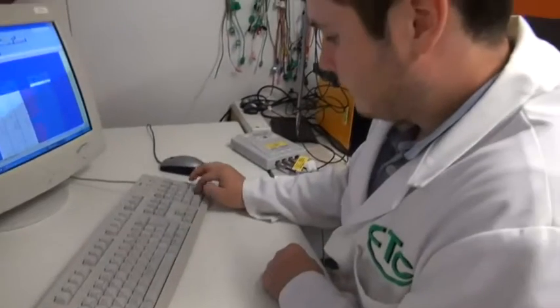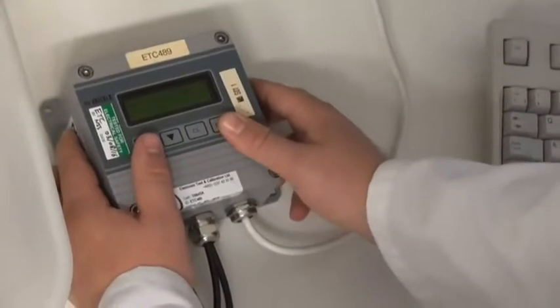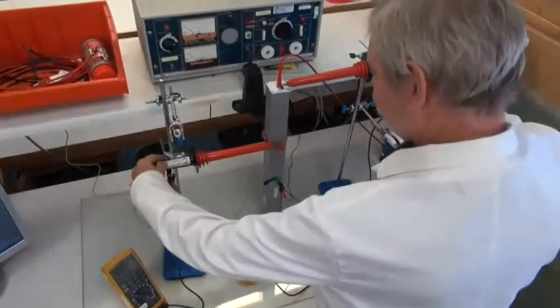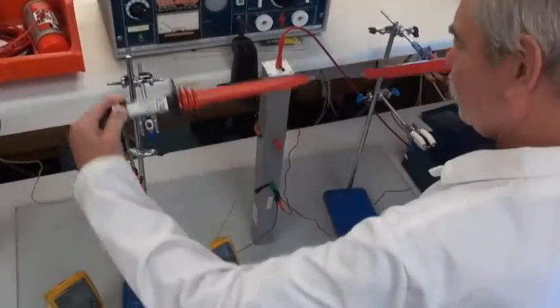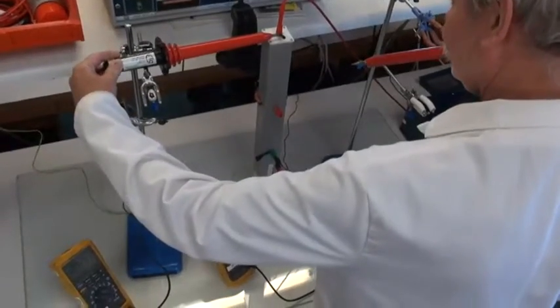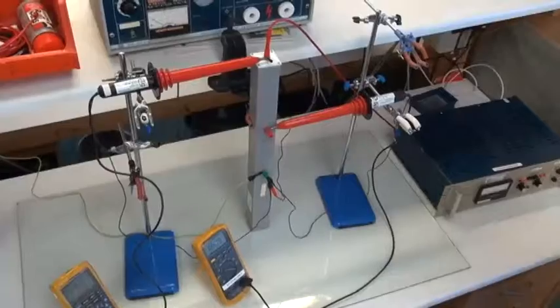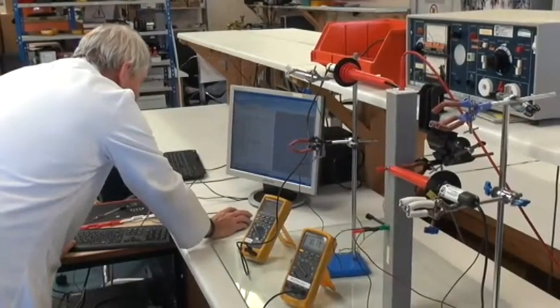Our reference standards are calibrated in other accredited laboratories ensuring all our equipment can be traced to national standards. We have 25 years history on some of our reference standards which means we can predict the drift on measurements on any given day, giving results many times more precise than the equipment's original specification.